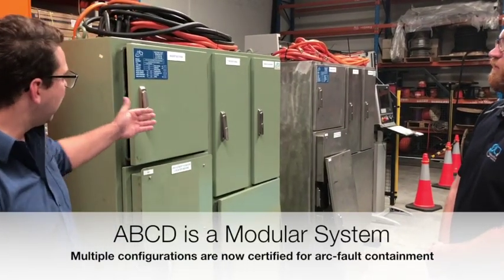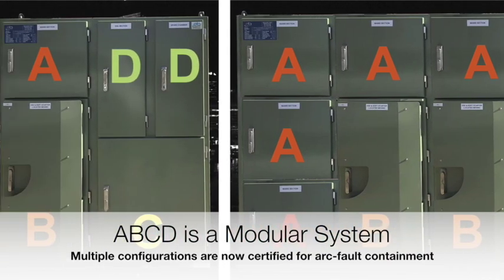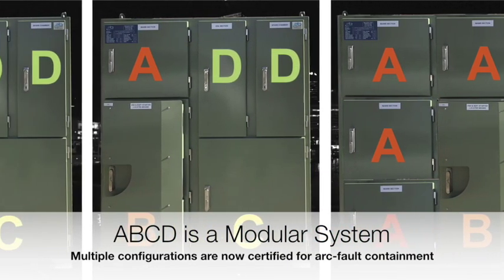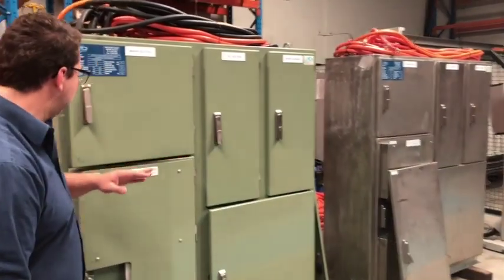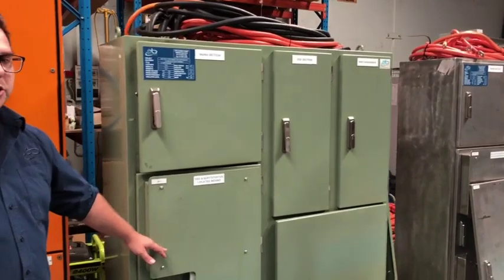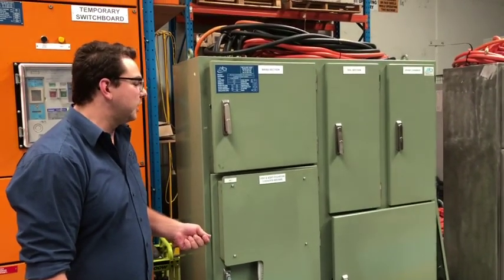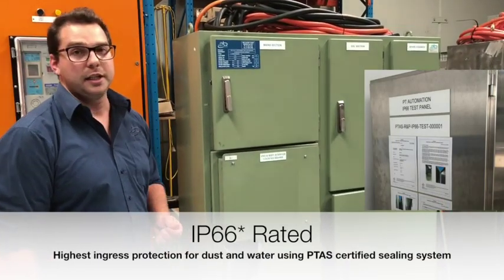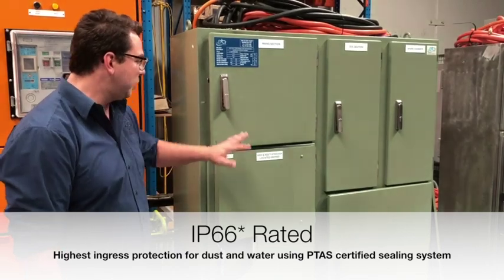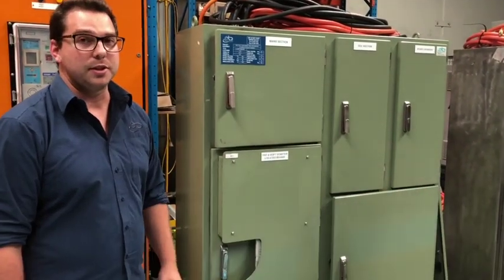For example, we could have a number of DOL and feeder sections depending on the pumps and feeders out in the field, along with distribution sections and VSD and soft starter sections. This board is rated at IP66 if we are to put a soft starter within the switchboard. If it is a VSD, we have a fascia which will mean it drops down to IP56.